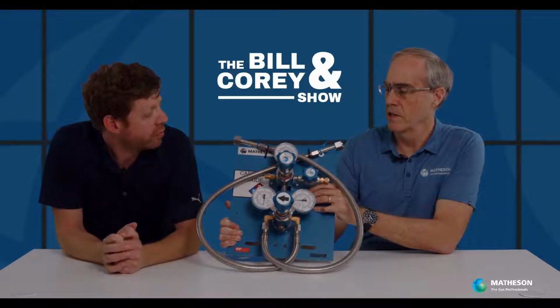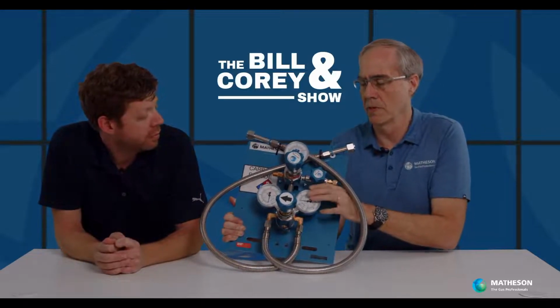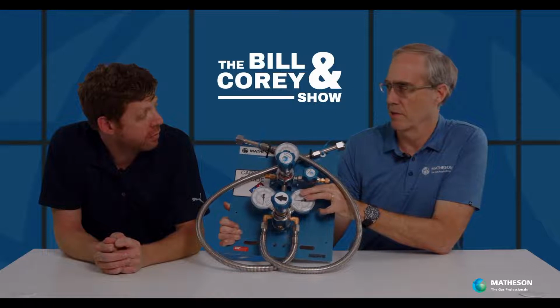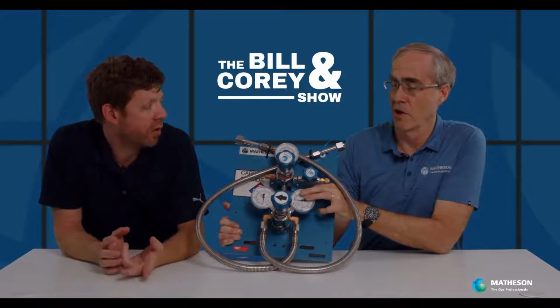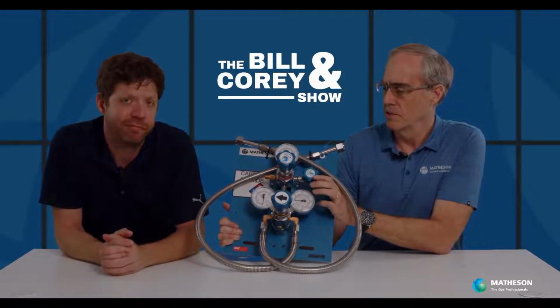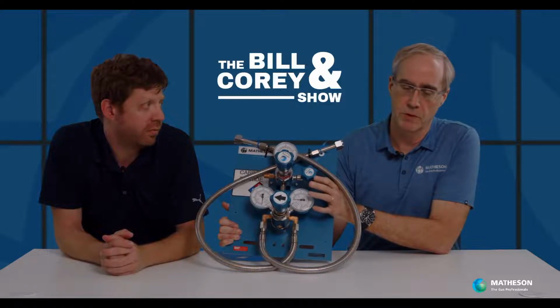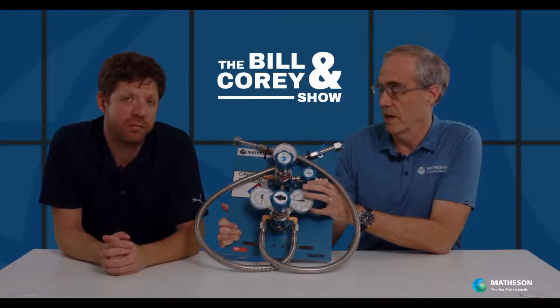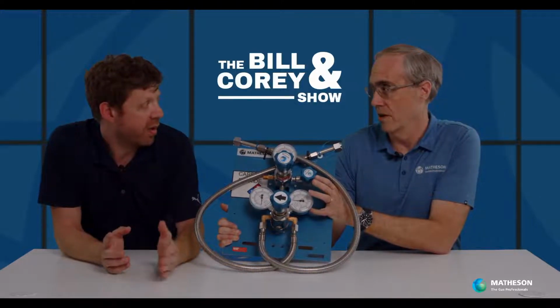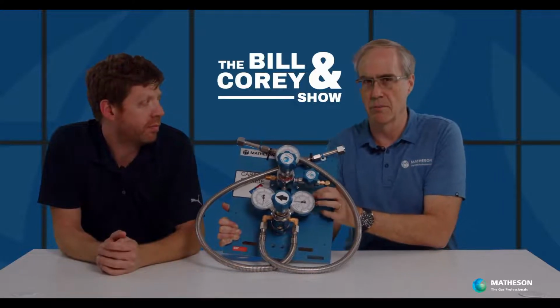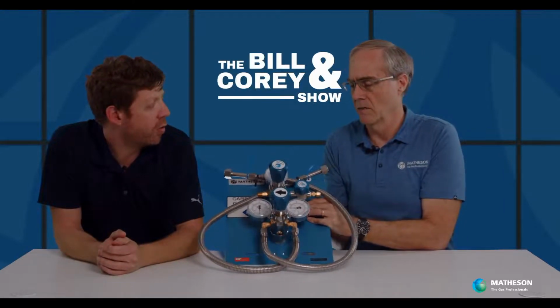For our standard 200 psi switchovers, your delivery pressure can be 30, 100, or 150. If you're doing a 230 psi dewar, then you can only have 125 and 30, because you have to have some pressure differential in there. Why couldn't you do a 100?